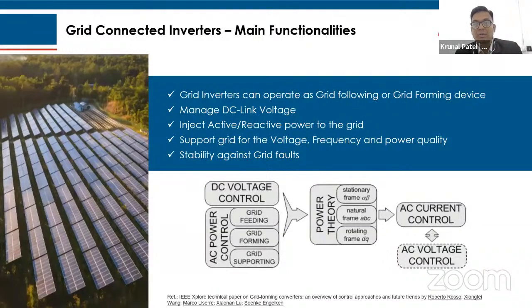Inject active and reactive power to the grid. This is the other part of the inverter, the AC side. While maintaining the DC voltage variation, at the same time we convert the active and reactive power according to the requirement of the grid, which is controlled either by the PPC controller or the microgrid controller. Support the grid for voltage, frequency, and power quality. As we all know, the grid forming inverter has a specific requirement to maintain the voltage and frequency within the specific limits and stability against grid faults.